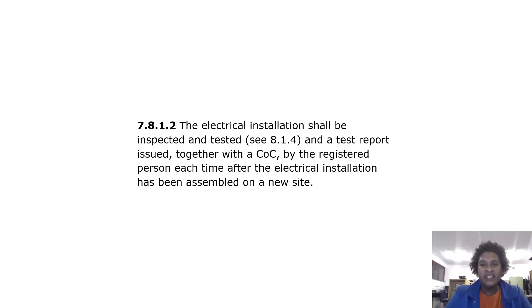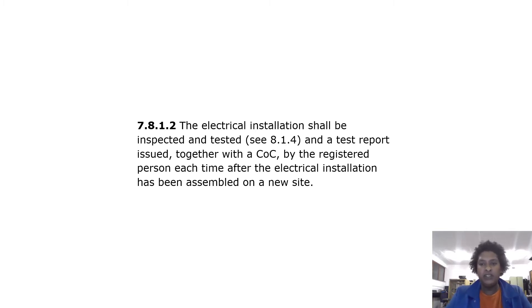The electrical installation shall be inspected and tested, see 8.1.4, and a test report issued together with the Certificate of Compliance (COC) by the registered person, each time after the electrical installation has been assembled on a new site.